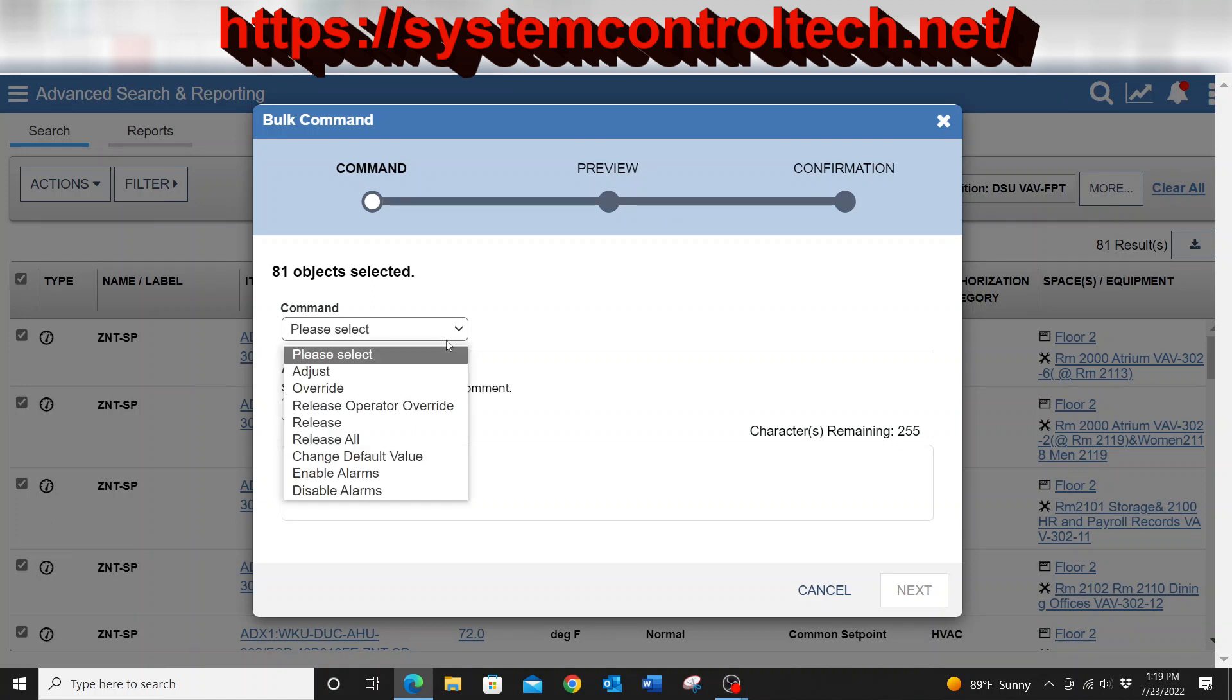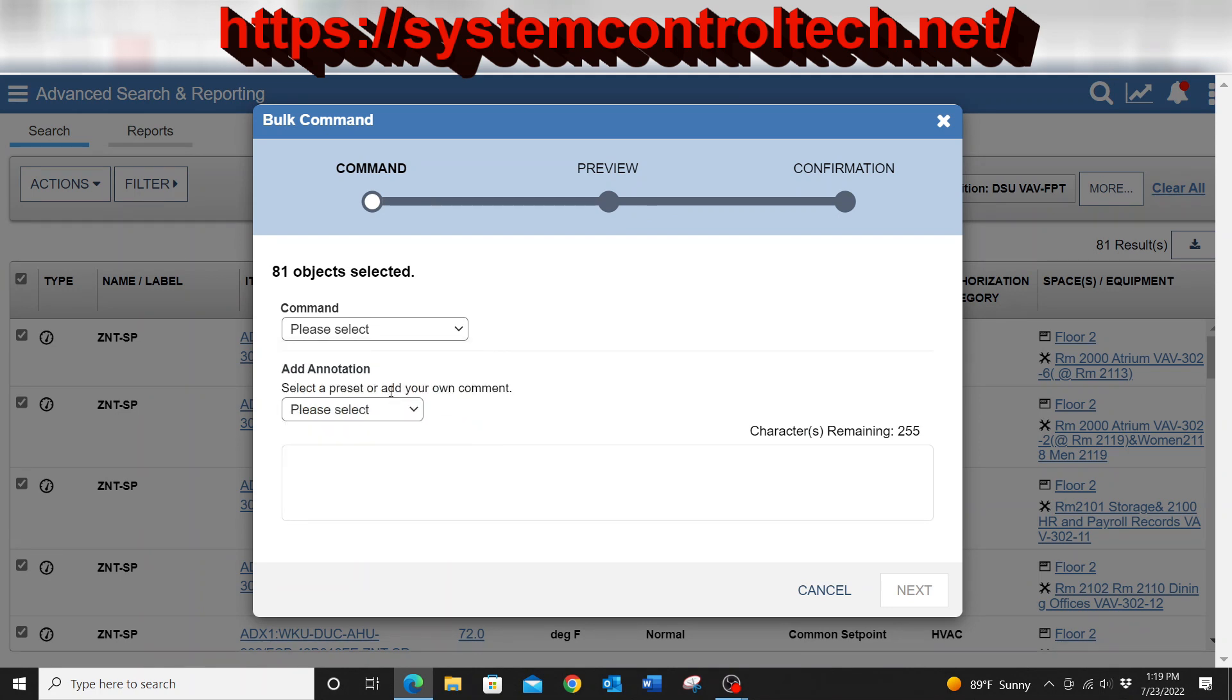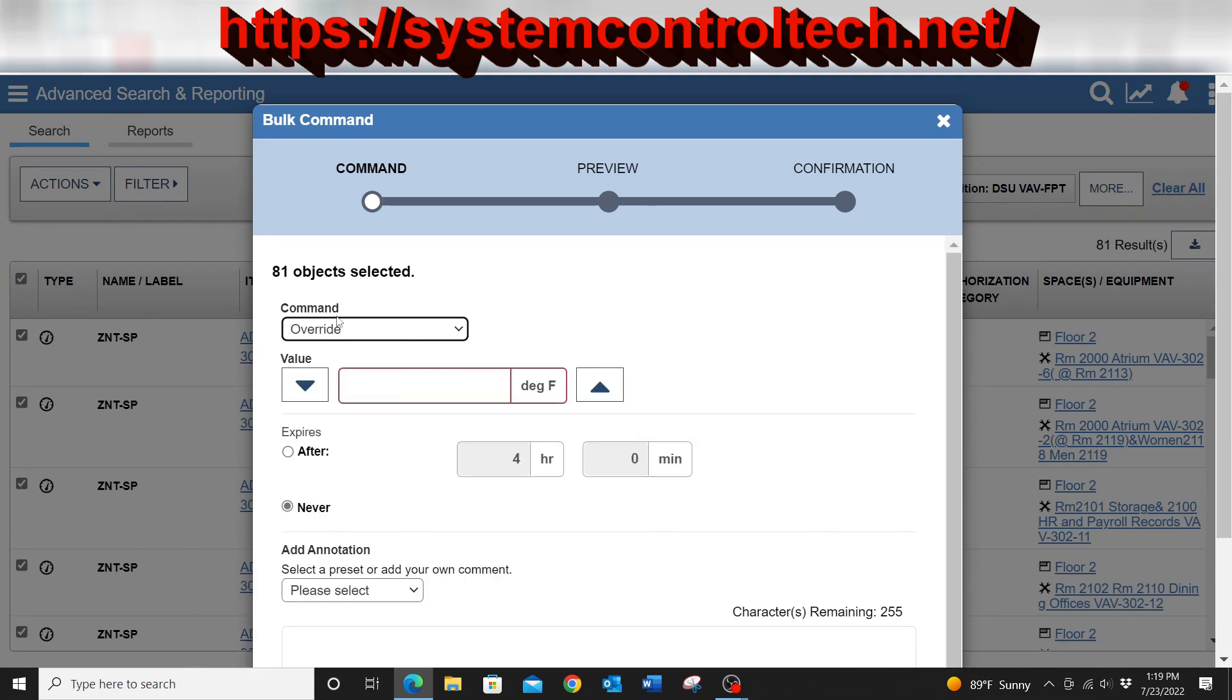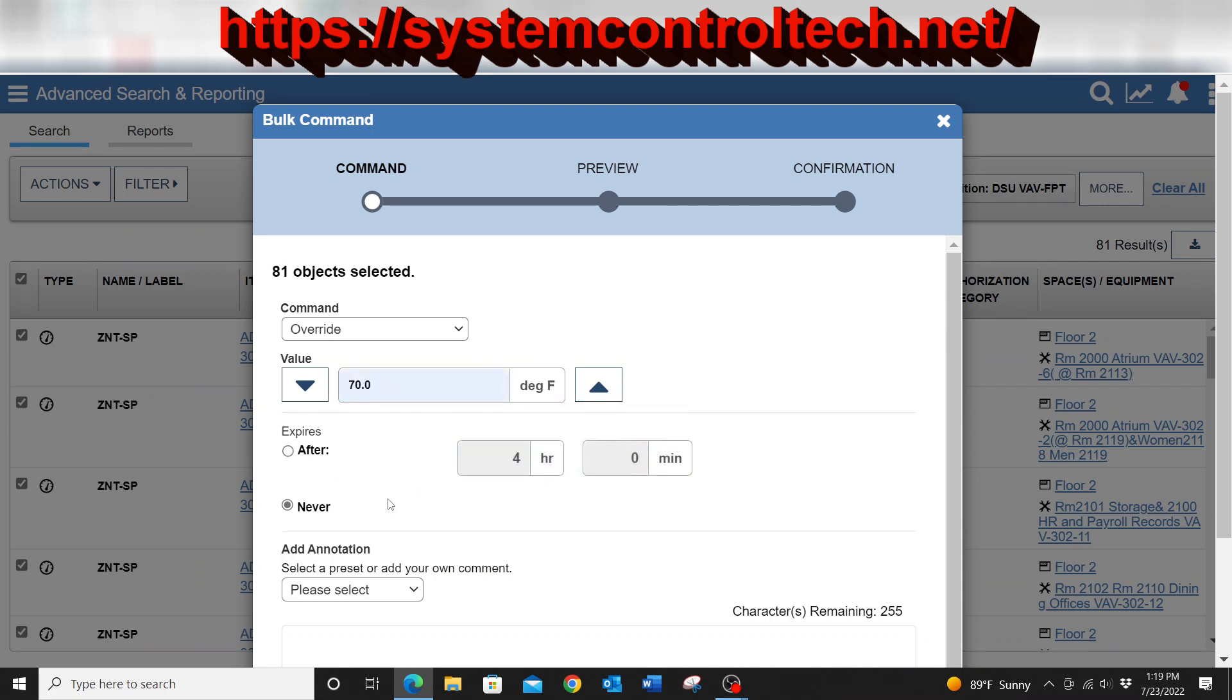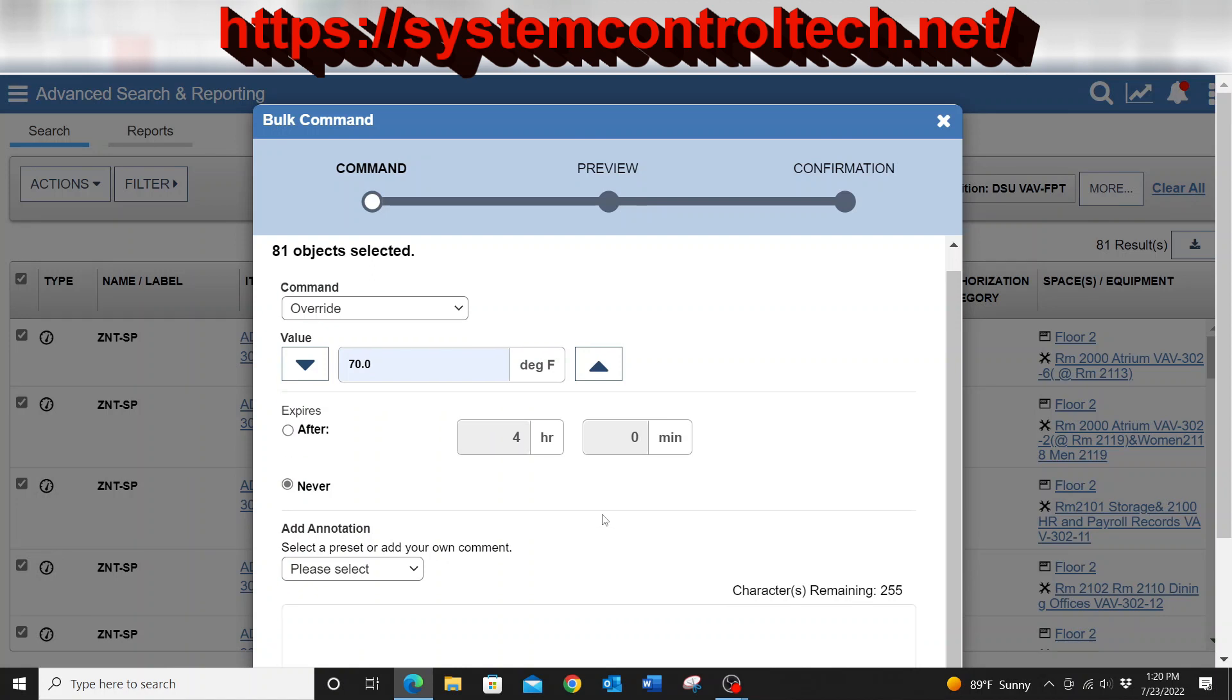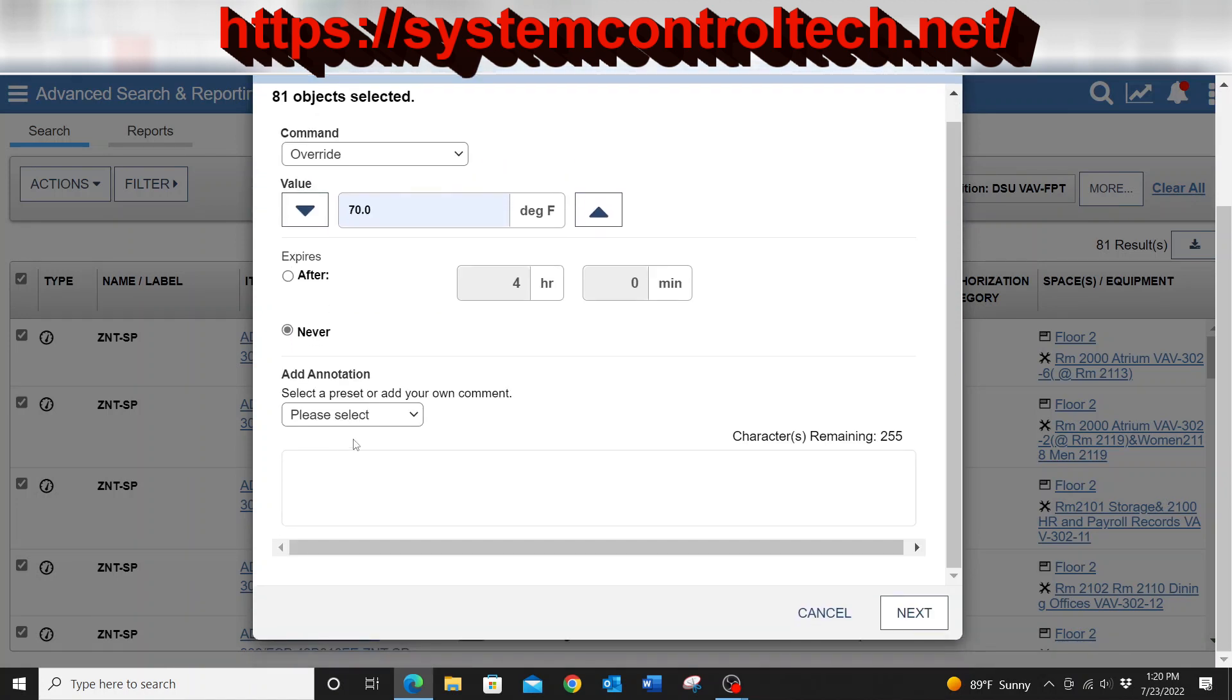From this, I have the option of doing an override. I can do an adjust or just whatever I need to do from here. For example, if I wanted to do an override and for example, change that to 70 degrees and just like that, and I can have it to expire after so long. Imagine if they were going to have a major event where the building is going to be heavily crowded. You want to bring that temperature down just a little bit to kind of help keep everyone from getting too hot. That is where this can come into play.